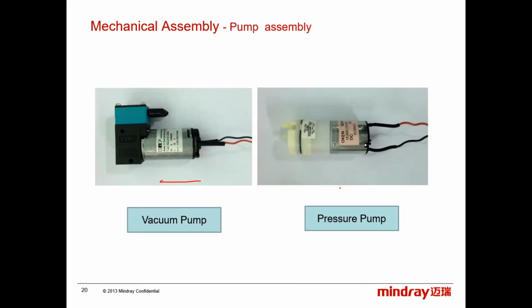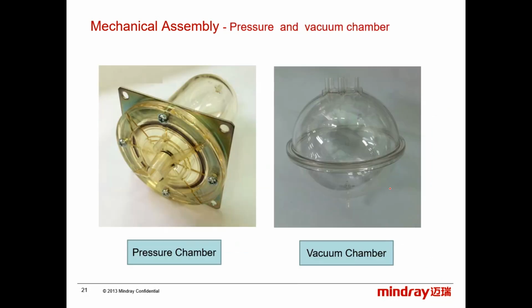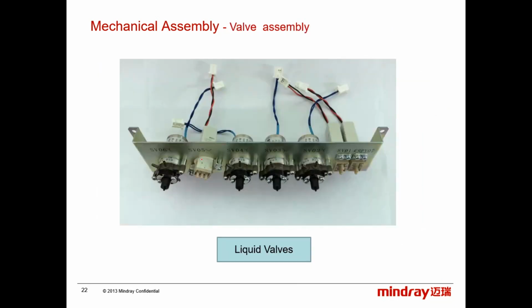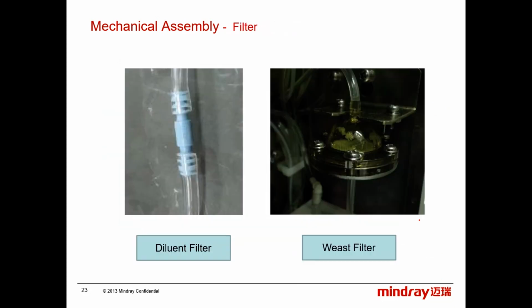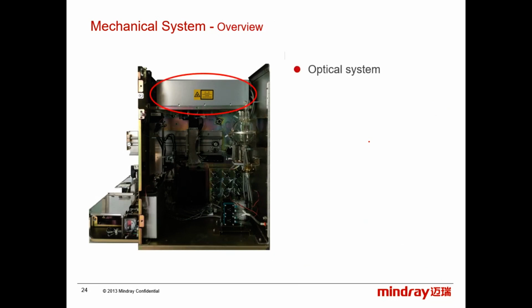This is the vacuum pump, and this is the pressure pump. We have a pressure chamber to store and stabilize the pressure, okay? And we have also the vacuum chamber for waste collection and vacuum creation. Liquid valves, okay, we have normal or generic valves and the LVM for high precision valves. Diluent filter and the waste filter, okay? This is the laser assembly, or the optical system, on the top. Sampling drive, okay, horizontal and vertical.